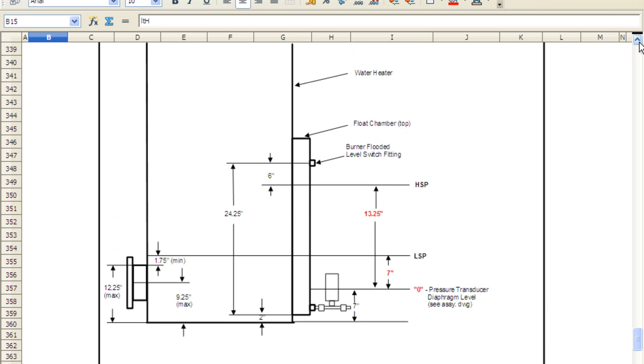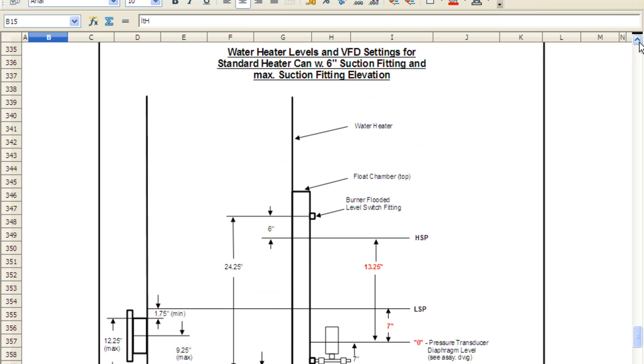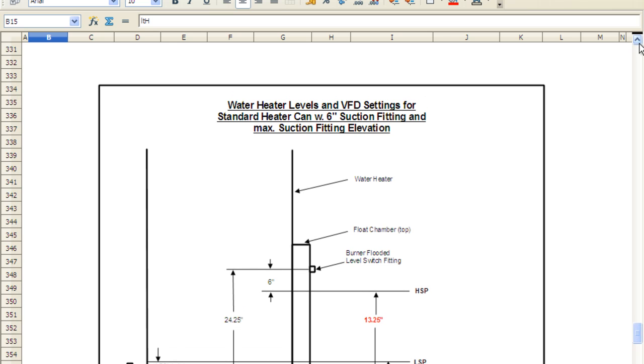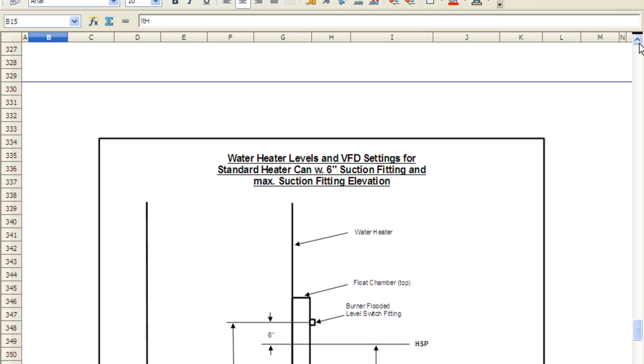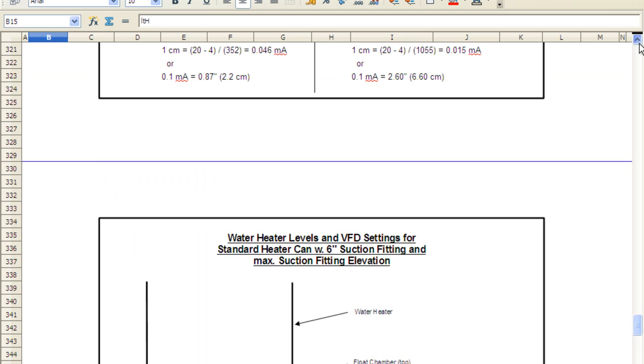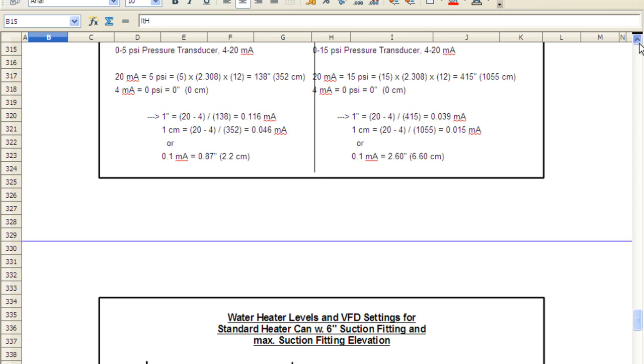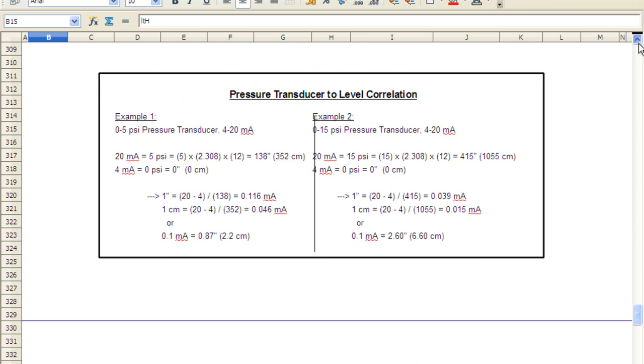But when you install a new transducer, sometimes you've got to adjust these numbers just a little bit. Raise them up a little bit, down a little bit, to keep it in a range to where the pump doesn't suck air on the suction or doesn't go to the burner flooded limit. Those two areas we're going to scroll up here to the parameter list.